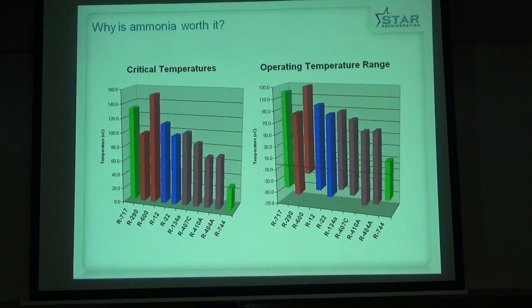It's the temperature where it no longer exists as both gas and liquid. And you can see the critical temperatures for lots of different refrigerants along the bottom there. The highest one, the third bar in the red one, is butane. Butane's fantastic, 150 degree critical temperature, but unfortunately not really suitable for industrial systems like this. The second highest, right on the left-hand side, is ammonia, 133 degrees C, critical temperature.